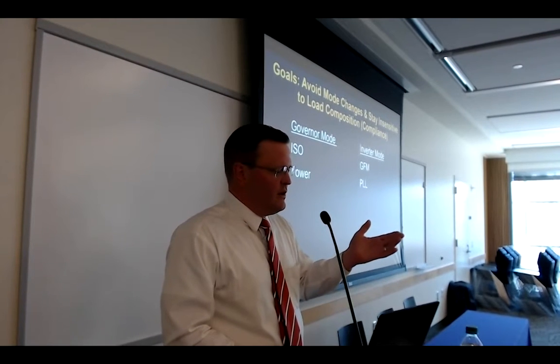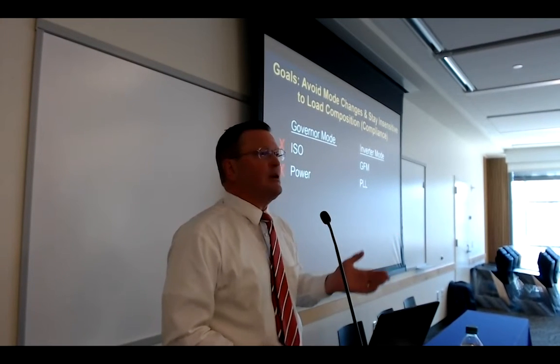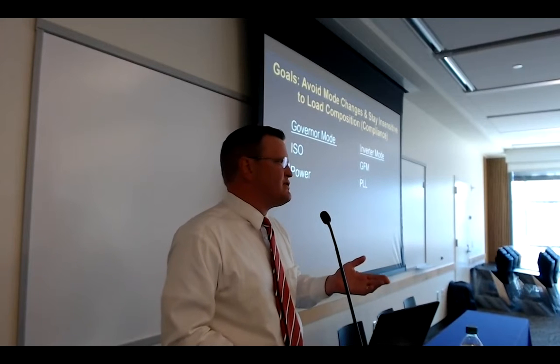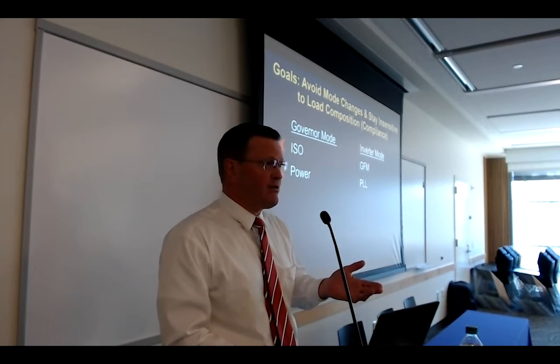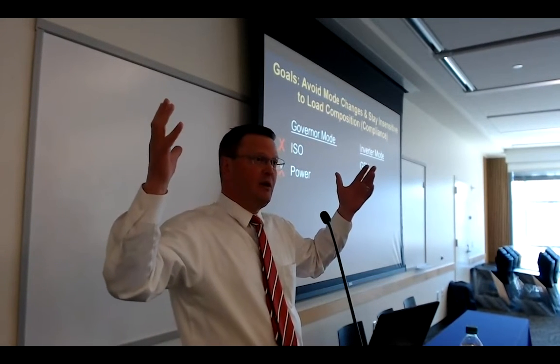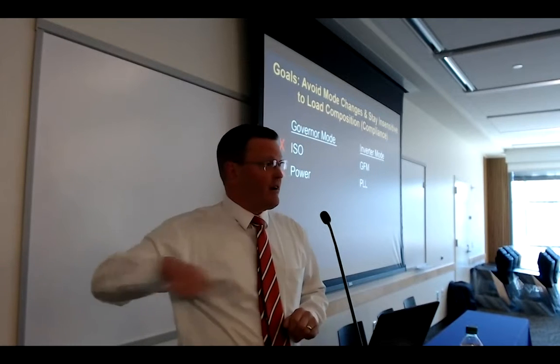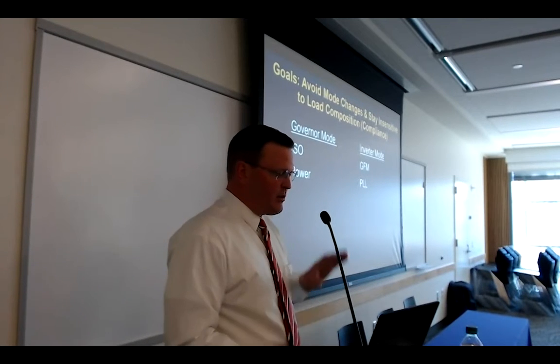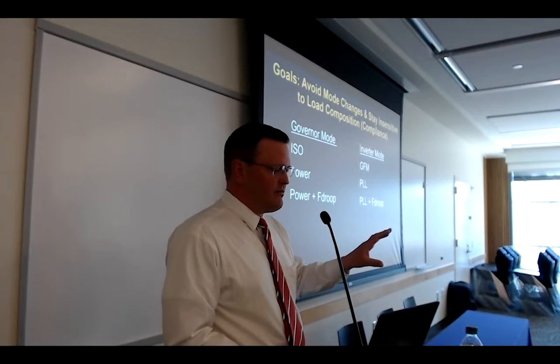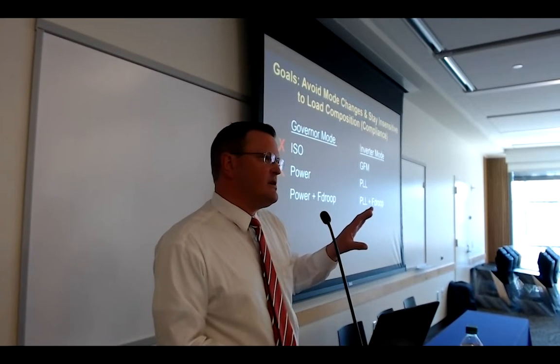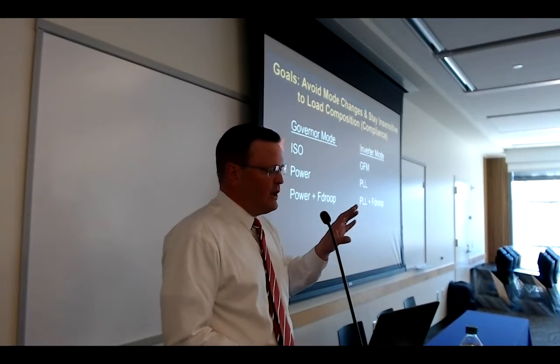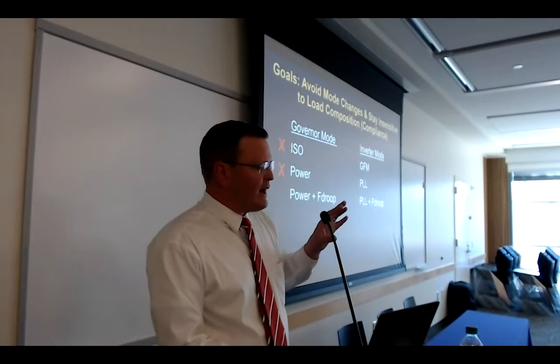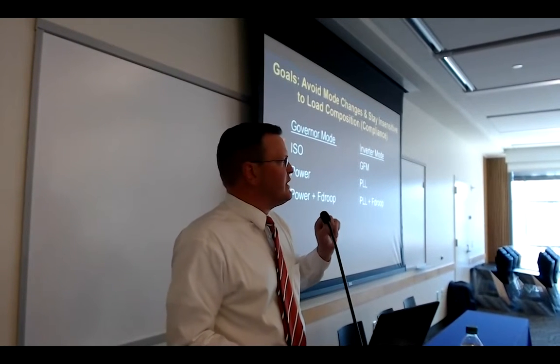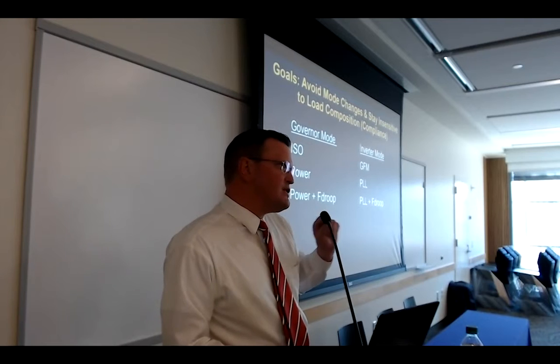Here we know that we can't take an isochronous generator and attach it to the bulk electric grid. We all know why. We also happen to know that steam turbines are primarily power sources. They're not very good at regulating frequency because they've got a big steam head to deal with, and the power is either going out the stack or out the electrons. So they're pretty much constant power devices, very similar to the phase lock loop, but they have a little bit of droop behavior.